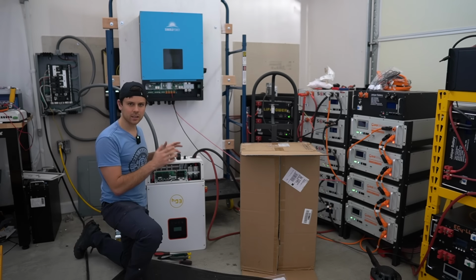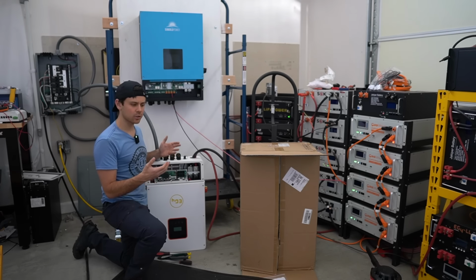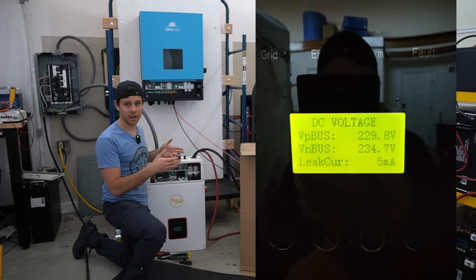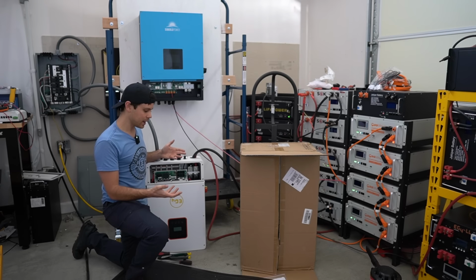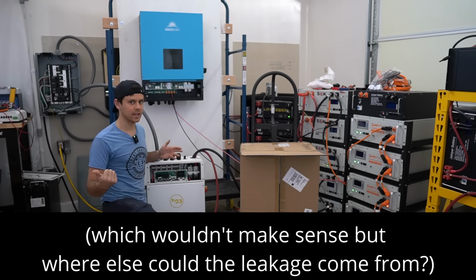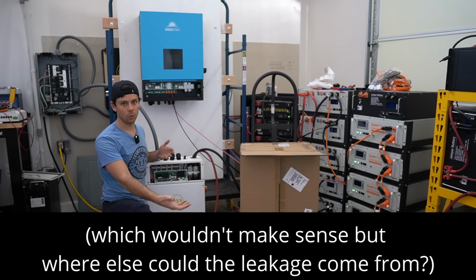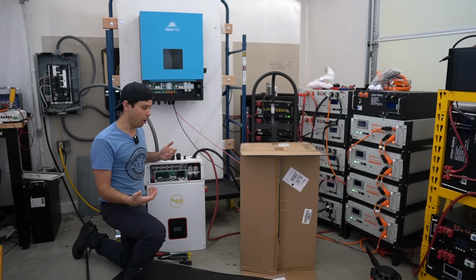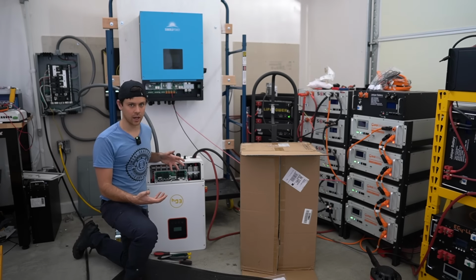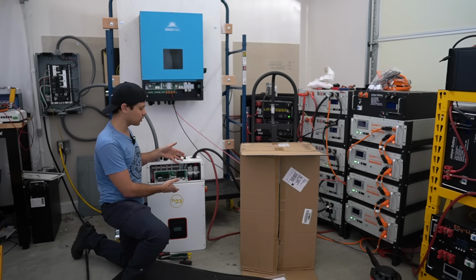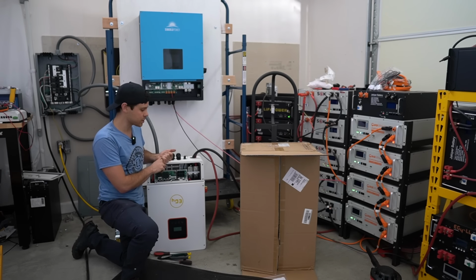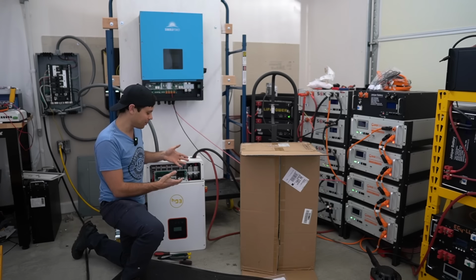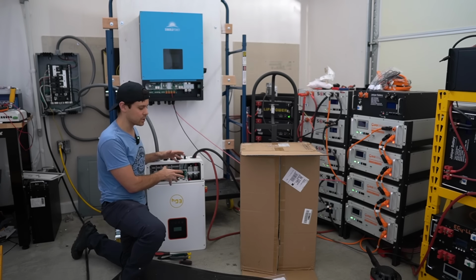Now this inverter has a display option that shows you the DC bus voltage of 240 volts, and it shows leakage current. And typically it shows 5 to 7 milliamps. And I was thinking maybe the electric vehicle charger was detecting a difference in some leakage on one leg and was pulling more current from one side than the other, and it was causing it to trip. Also, these inverters have their own GFCI. So this morning, with the help of Signature Solar, I disabled GFCI and some other options, and we're still having the same problem. So Signature Solar is setting up the exact same issue that I'm having and seeing if they can fix it on their own.